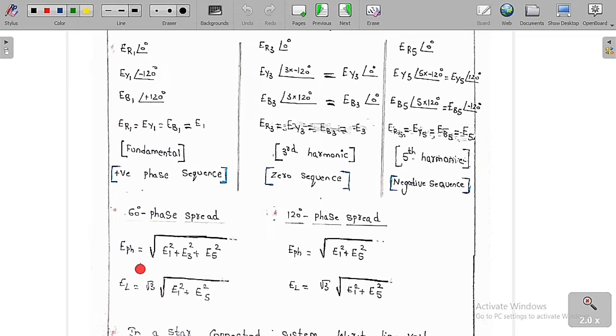So therefore we can say E phase is equal to root over E1 square plus E3 square plus E5 square, whereas EL is equal to root 3 times root over E1 square plus E5 square, because in the line voltage there will be no third harmonic components. Now if you go for the 120 degree phase spread, then E phase is equal to root over E1 square plus E5 square, so there will be no third harmonic component, and EL is equal to root 3 times the phase voltage, which is root over E1 square plus E5 square. So these are the important formulas that you need to remember for 60 degree phase spread and the 120 degree phase spread, the phase voltage and the line voltage expression.